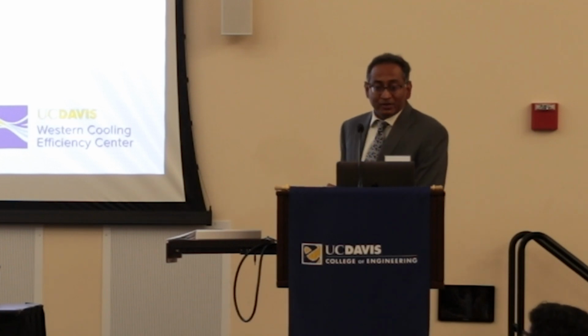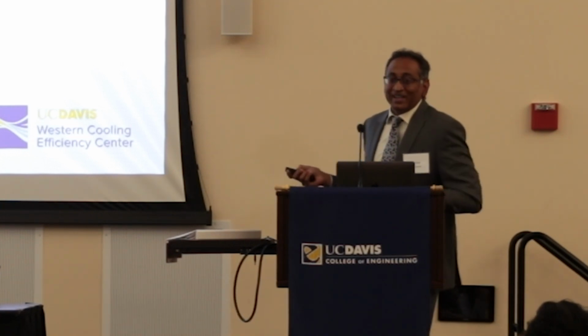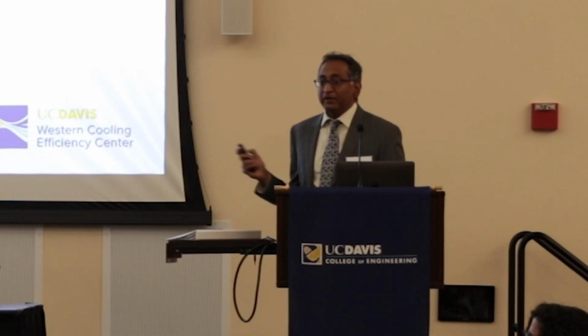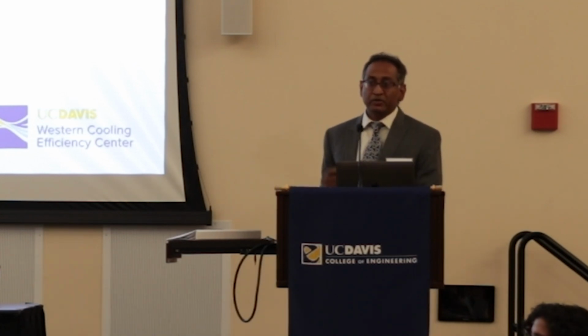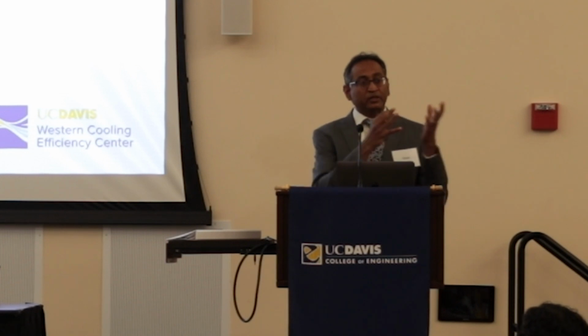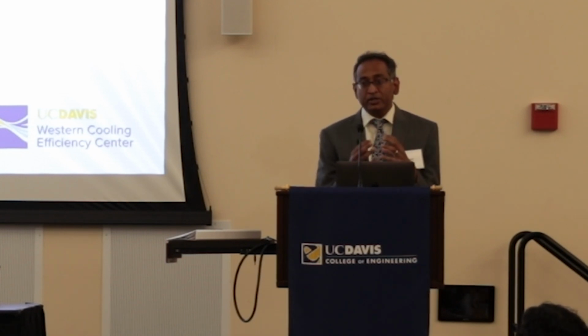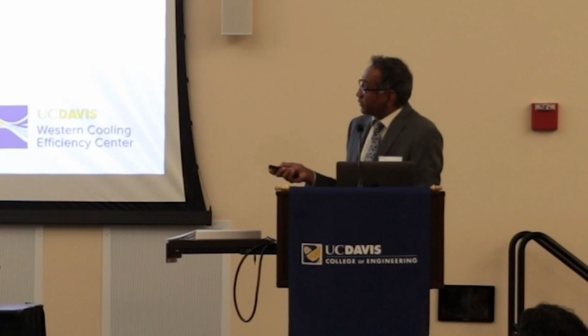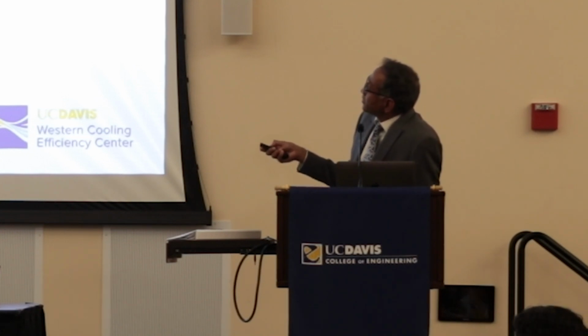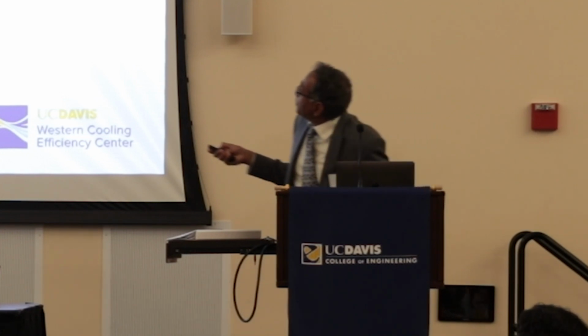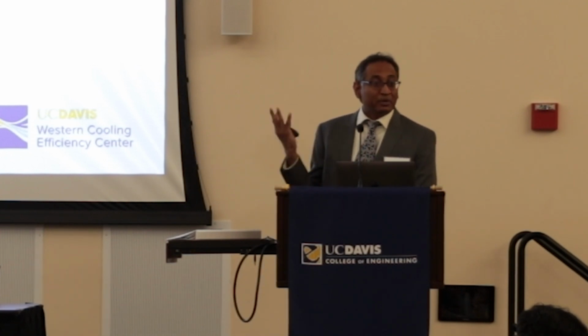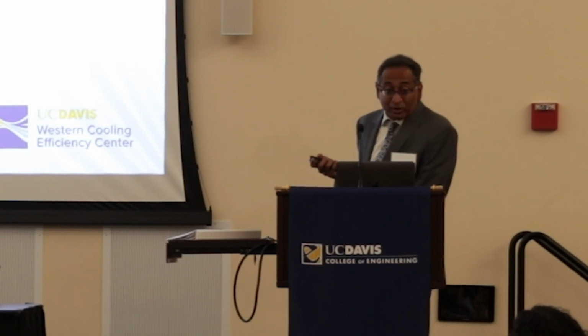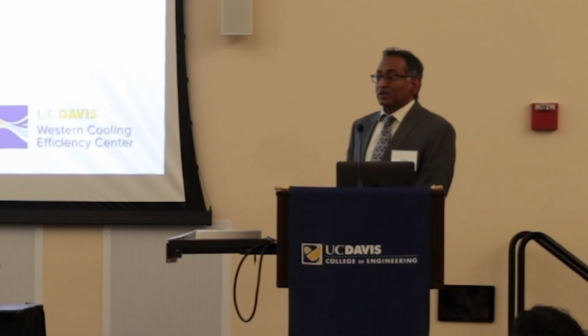I want to move to data centers. Oops, I see you red there, but it's important. On the top left here is what's called the power use effectiveness of a data center. So basically, all the electrical energy going to the data center divided by the electrical energy going into the servers. It's not a perfect metric, but what you'll see is that over the years, the PUE has gone down, and it's about 1.5. That means 50% of the energy is still used for other things than compute. And that's not good, because we are expecting 390 terawatt hours of electrical energy going to data centers by 2030.